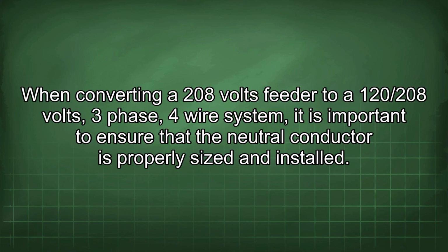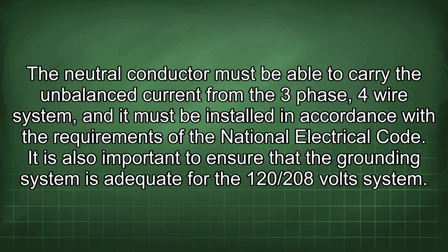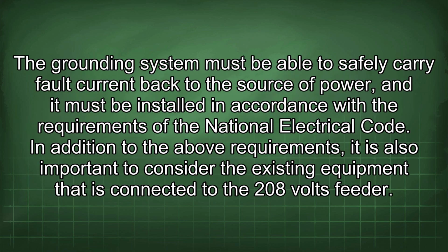When converting a 208 volts feeder to a 120/208 volts 3-phase 4-wire system, it is important to ensure that the neutral conductor is properly sized and installed. The neutral conductor must be able to carry the unbalanced current from the three-phase, four-wire system, and it must be installed in accordance with the requirements of the National Electrical Code. It is also important to ensure that the grounding system is adequate for the 120/208 volt system. The grounding system must be able to safely carry fault current back to the source of power, and it must be installed in accordance with the requirements of the National Electrical Code.